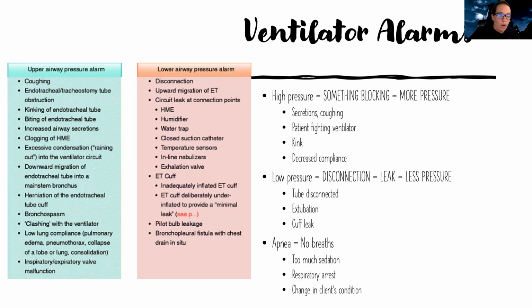There's also low pressure alarms, which means a disconnection. So this is the opposite. Before there was too much resistance. With low pressure, there's no resistance. Something's open or disconnected. So this happens when the tube gets disconnected. So if for some reason the tube gets disconnected from the ventilator, that can happen. Or if the patient pulls the tube out, or if there gets a hole in the tube, which can happen because there's a balloon when we insert the tube, we inflate a balloon, and that can get a hole in it. And this can all lead to a low pressure alarm. So in other words, high pressure, resistance, blockage; low pressure, disconnection or leak. There's an issue with not enough pressure.